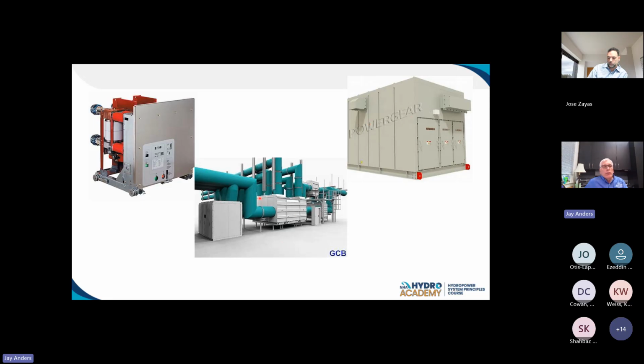This right here, you've got your isolated phase bus. This bus would go over to a generator, and then it would come out of the generator, out of this generator breaker, go on over to your step-up transformer. This device right here would typically have cables coming into it, though you could have bus work come into it too - I've seen that before. But typically this thing, think of it as your big old light switch for the generator, and it has a lot of automatic features to turn it on and off, to get it paralleled.